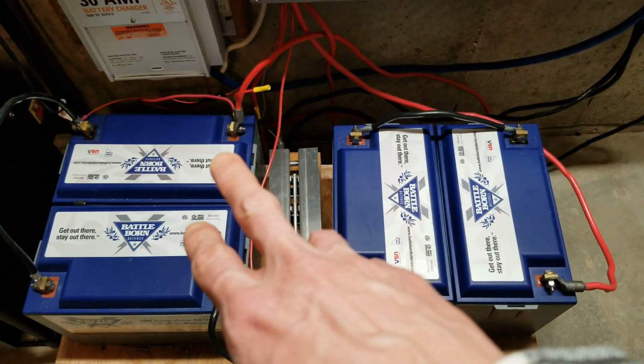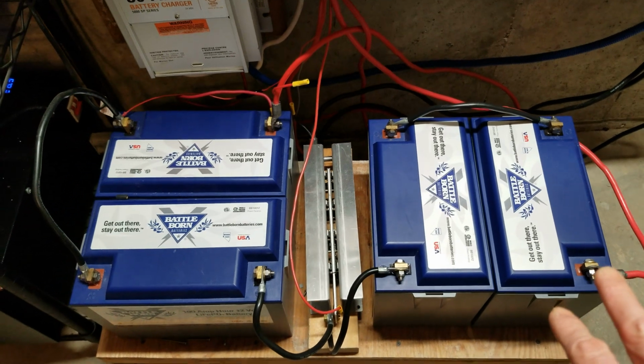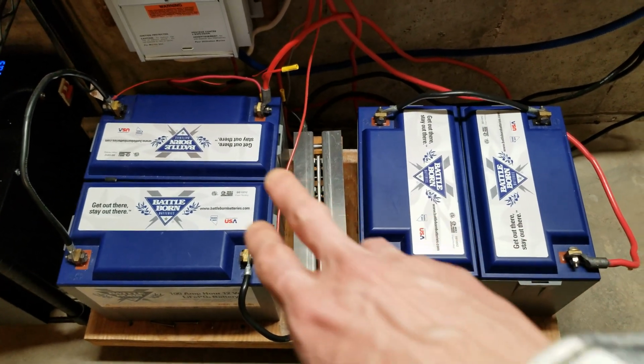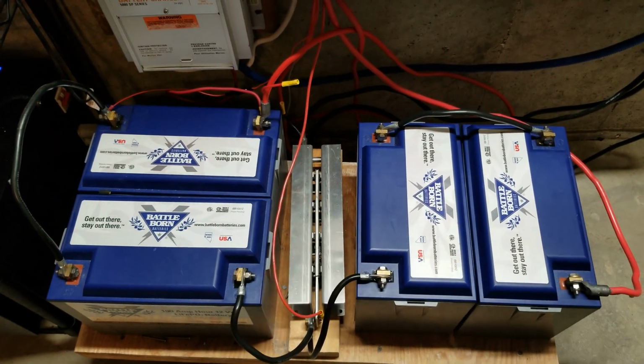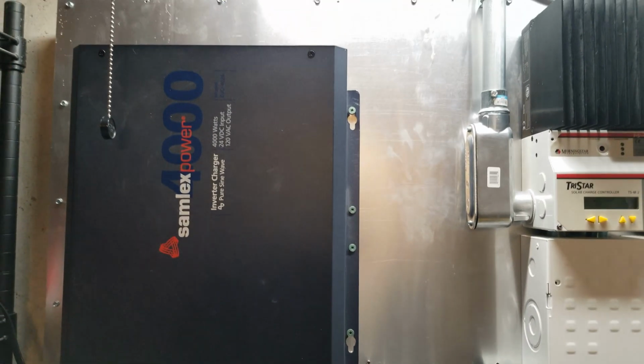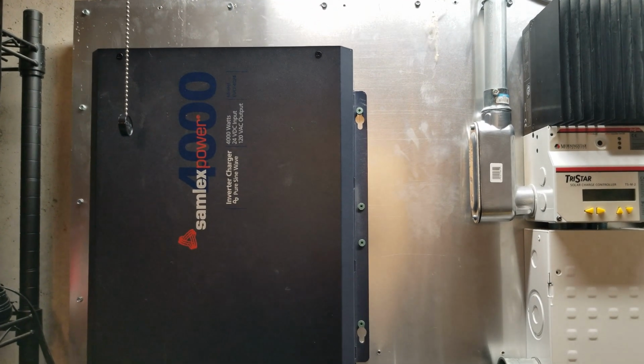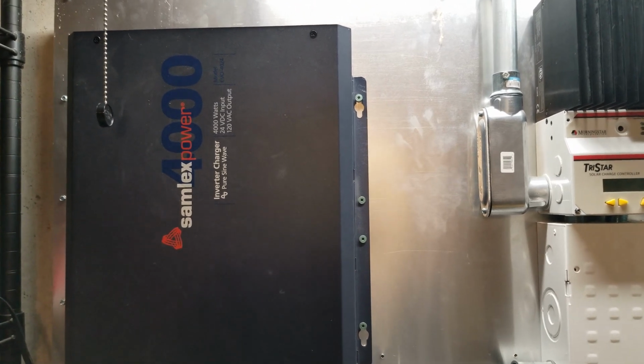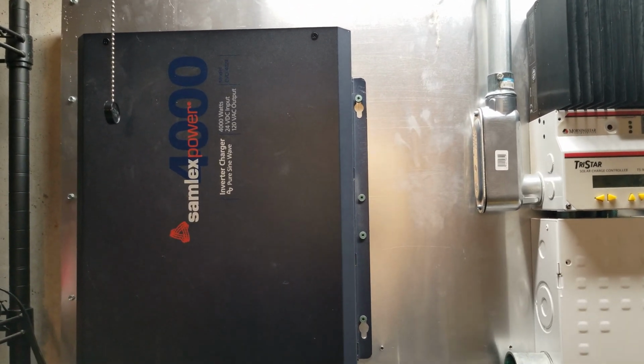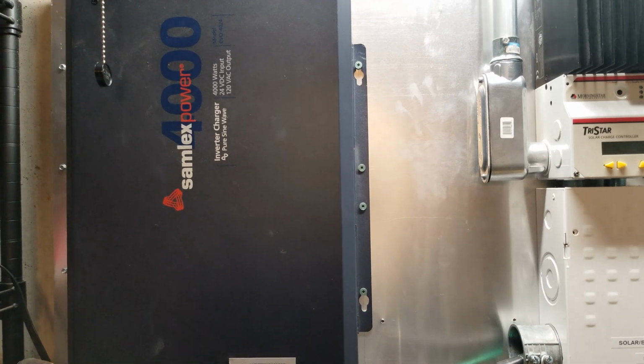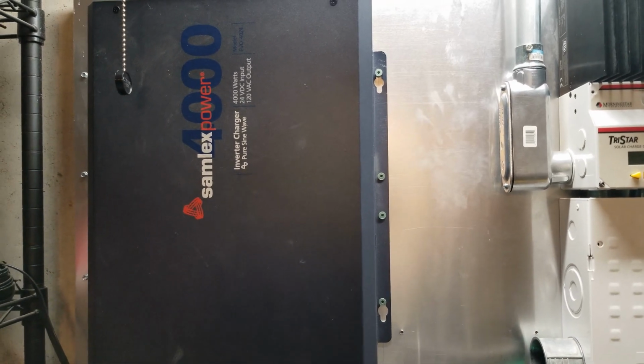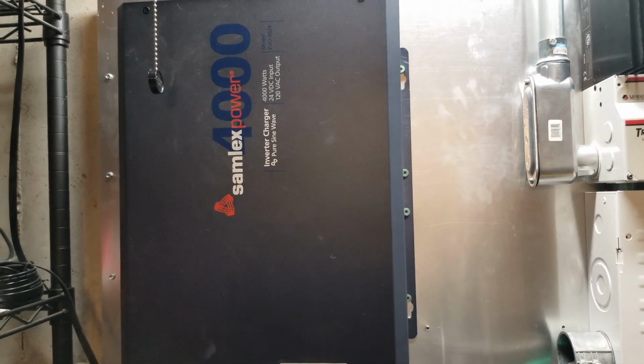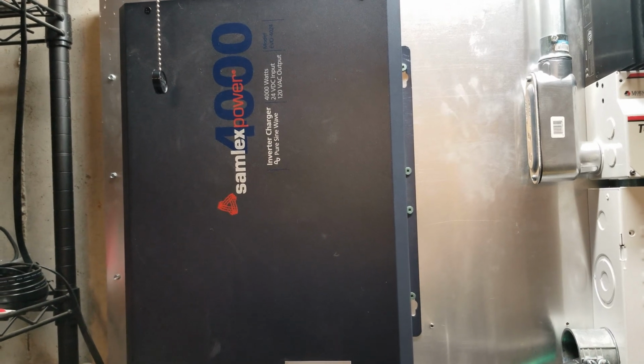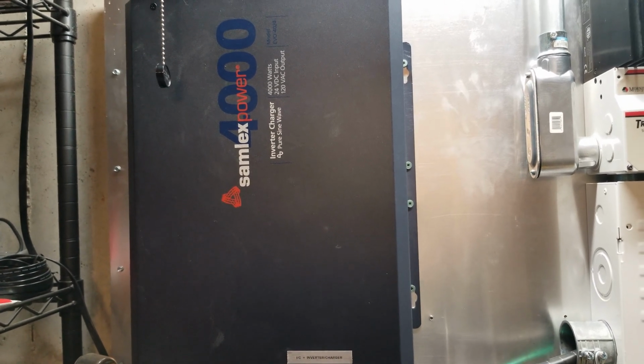Especially if you have less than... I originally bought two batteries, so that was obviously undersized for a 4,000 watt 24 volt inverter, which is designed to pull at max about 160 to 170 amps. And even then, a lot more than that for some of the surge conditions. I think it can do 200% of power for several minutes.